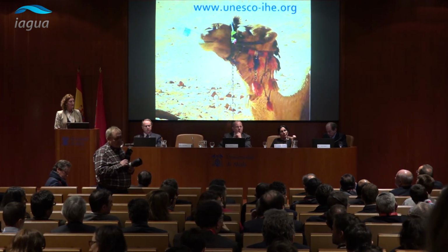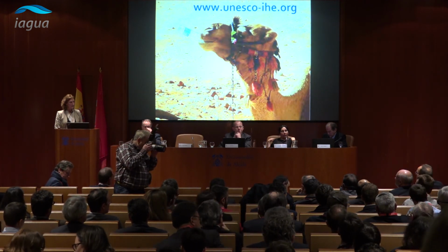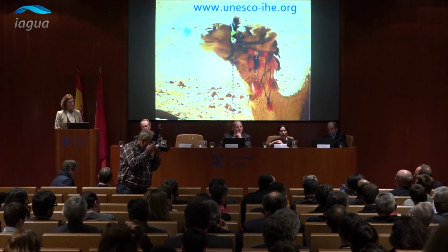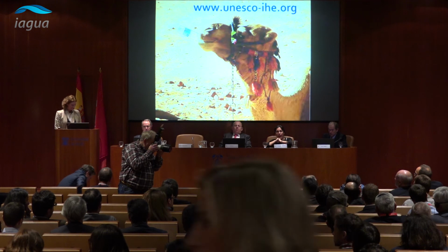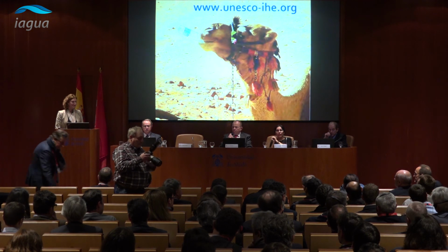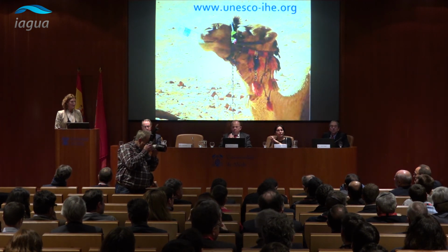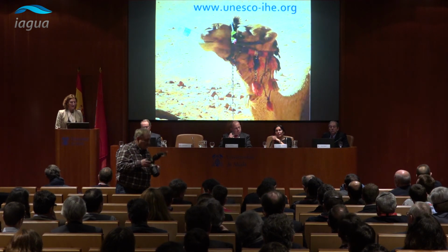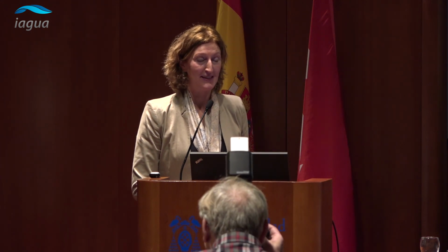It's clear from your presentation that the concentration of TEP becomes a critical component of the fouling in the UF surface. So are there any effective online measurements for TEPs that can be used on an industrial operational site? No. It's a very difficult method. I believe Acciona have one of their staff, Teresa Della Torre. She also has done quite some research on TEPs. It's a very laborious method, really, and difficult to get reproducible results. It's actually semi-quantitative, I would say.